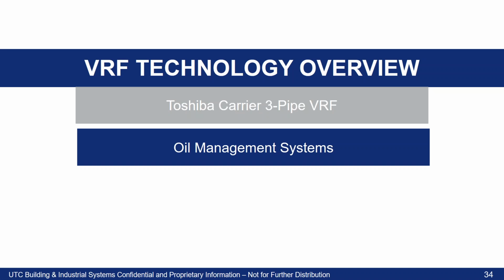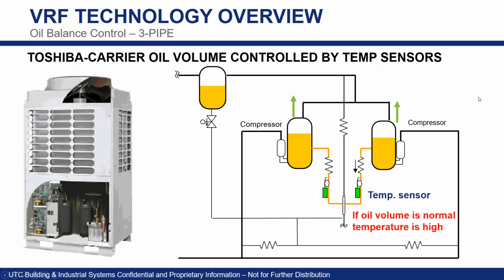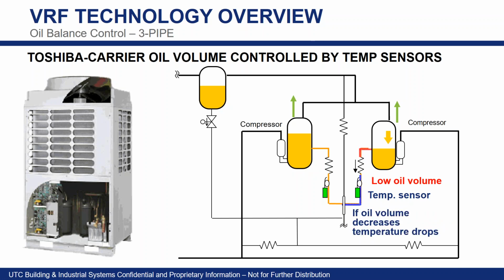Oil management. This is important to TOSHIBA-Carrier. This is something that we always try to educate our customers on, and that TOSHIBA-Carrier is huge on oil management. We always want to make sure that our compressors are seeing proper oil levels, okay? See, it is a complex system. Probably really don't need to get into the weeds too much on this, but essentially there is an oil separator here for if there is any issues with oil levels in our compressors, the system will appropriately distribute the oil. It's a little depiction there of what happens.